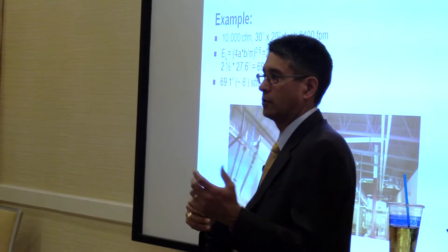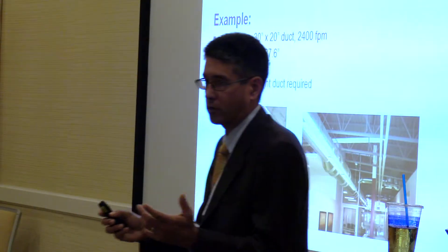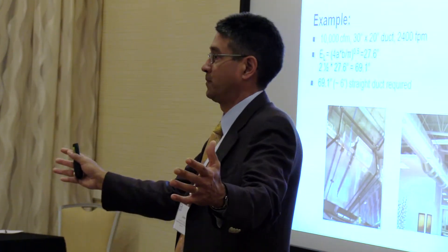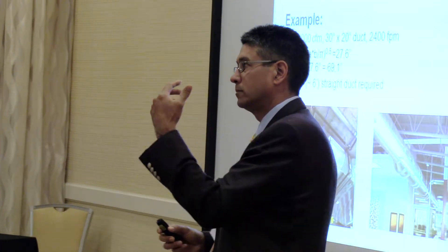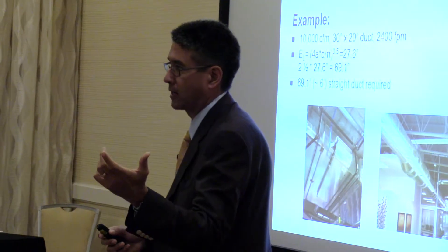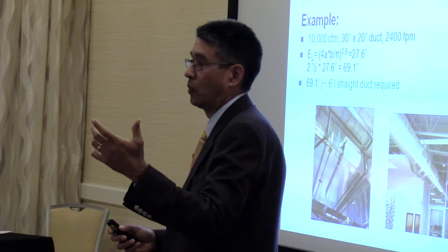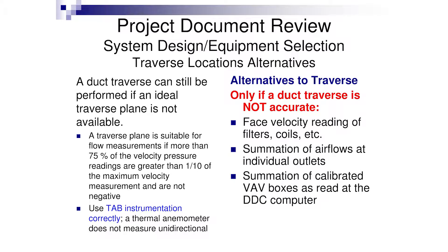Look at the drawings and documents — where are we putting air handlers? We know how easy it is to say to architects: give me more space. If you give me a larger equipment room, I can get a straighter duct run for more accurate air flow measurements. A nice study came out on that — looking at equipment space and the cost benefits of straight duct runs.